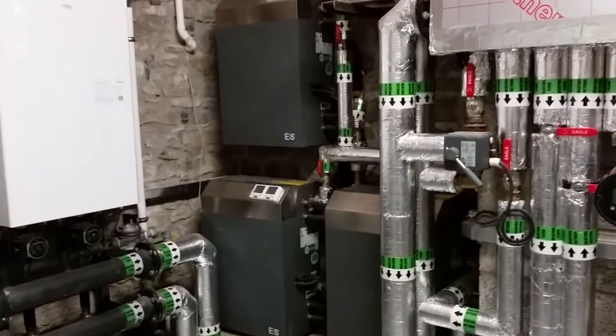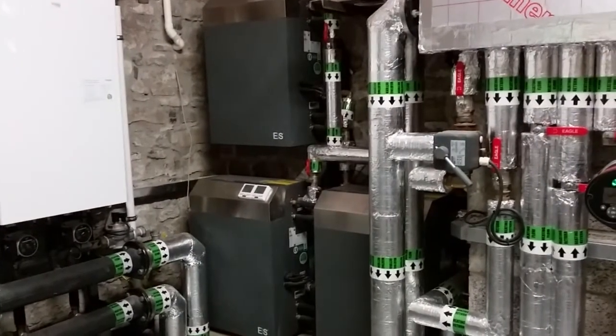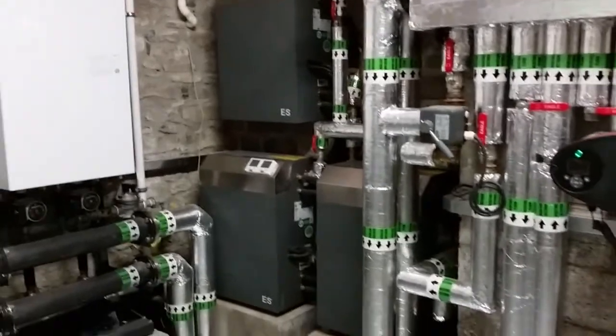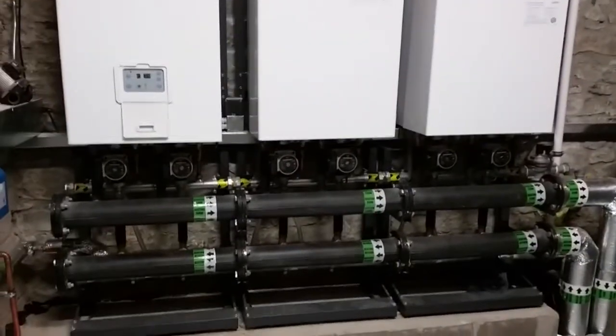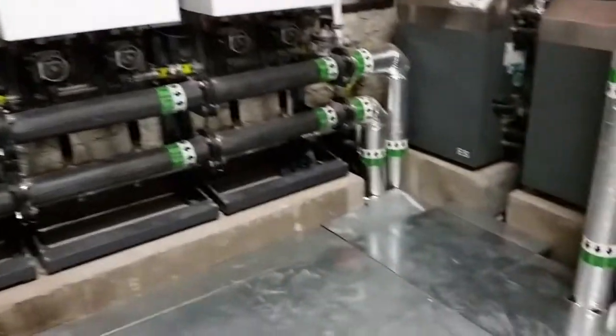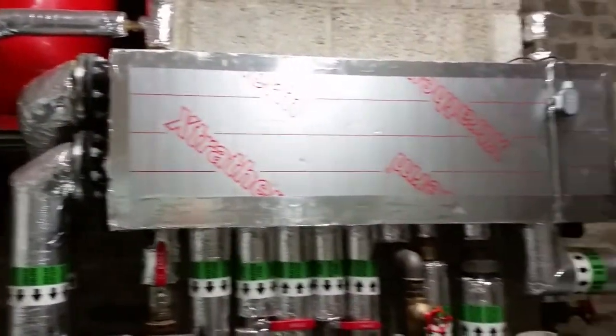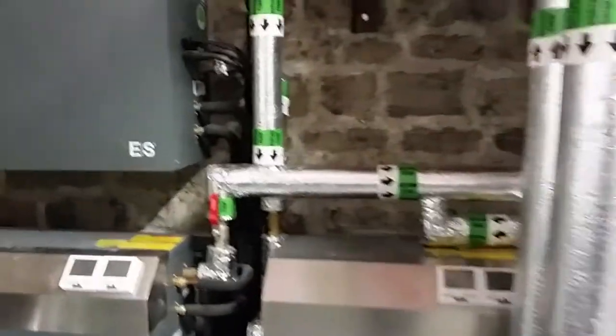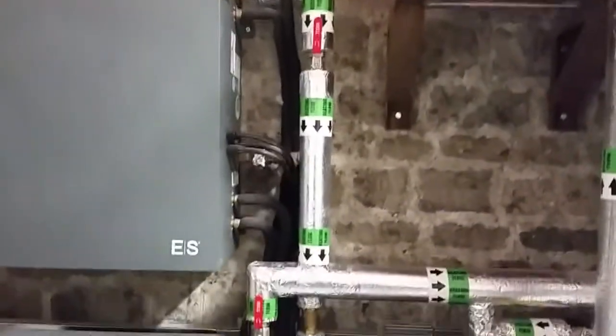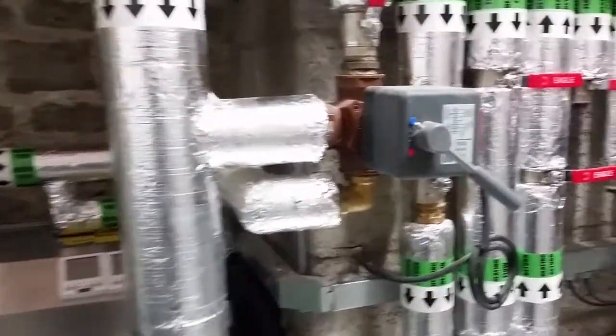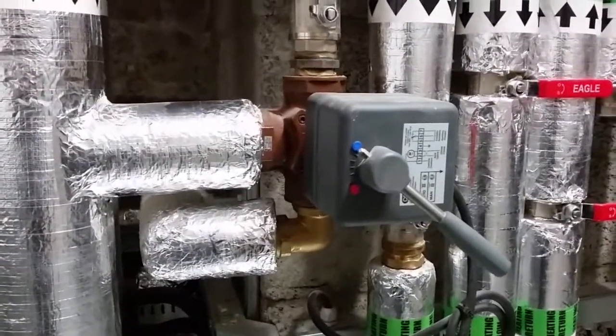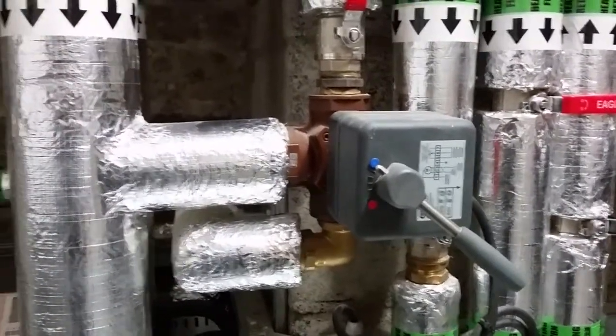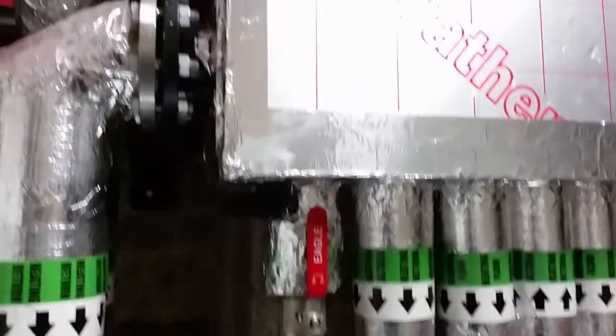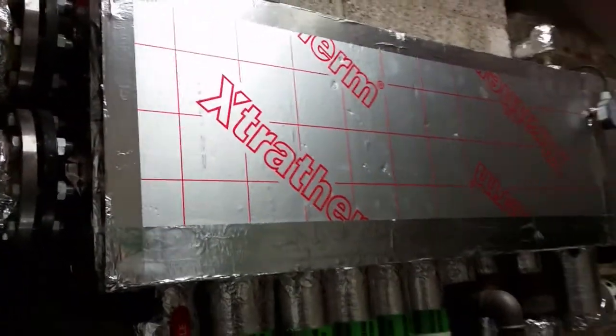Each have heat exchangers in the boiler house and heat collectors fitted outside behind the rear wall of the boiler house. The pipework from the main gas boilers feeds down under the floor and back up into the manifold distribution system, whereas the returns from the heat pumps are collected together and are directed back towards the energy zone manifold through a 3-port valve. The 3-port valve in position 1 will allow the flow to rise up into the manifold, and therefore the heat pumps can satisfy the heating load.